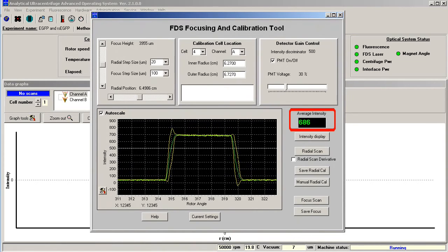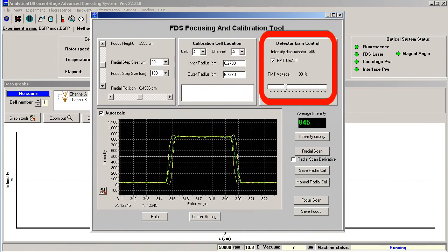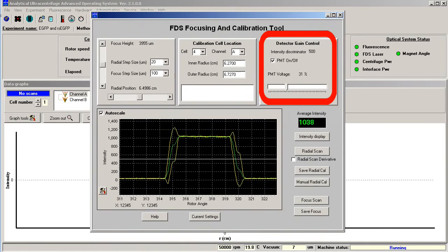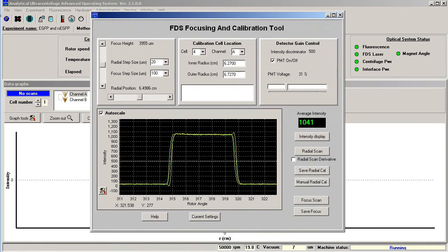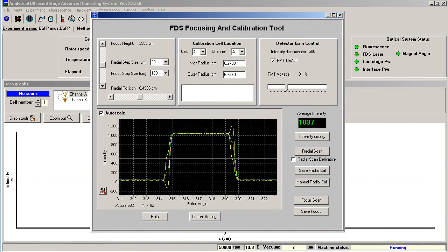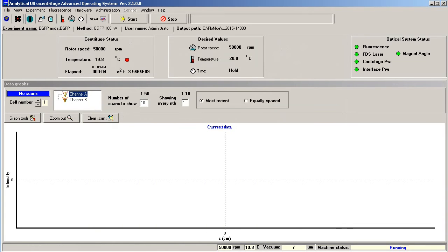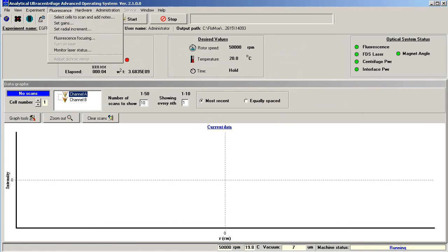To adjust the fluorescence intensity, select the PMT voltage bar. The sensitivity of the system's detection is regulated by PMT tube voltage, and the signal can be further amplified by gains. To obtain the proper signal, you need to adjust PMT tube voltage and gains.